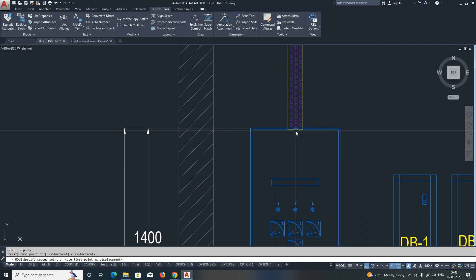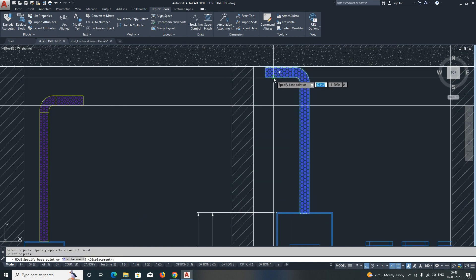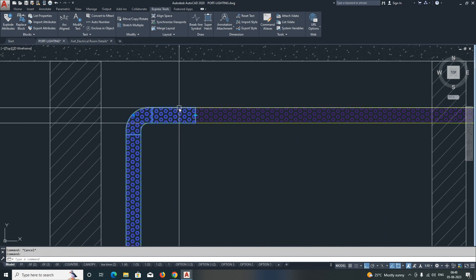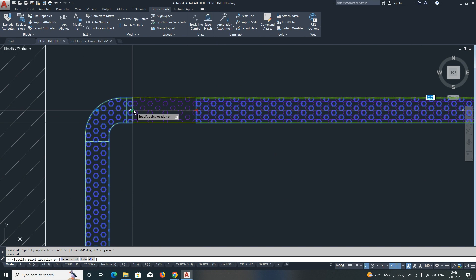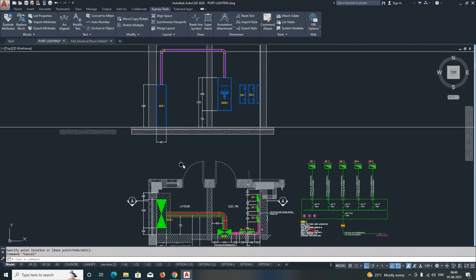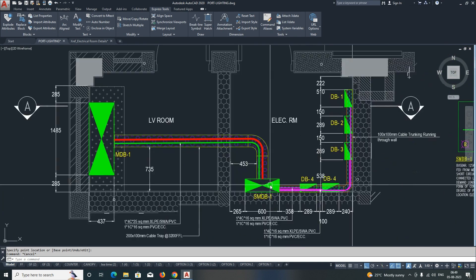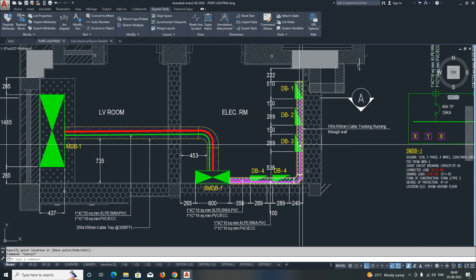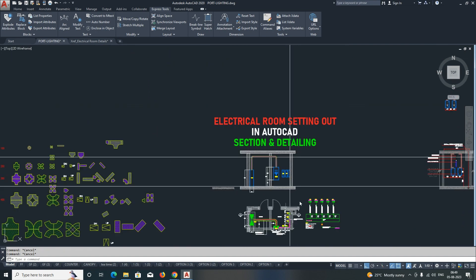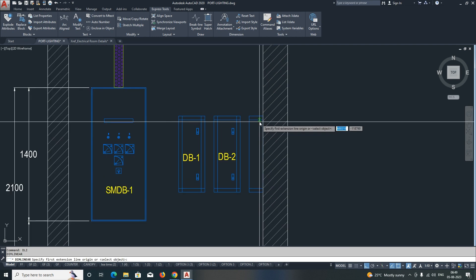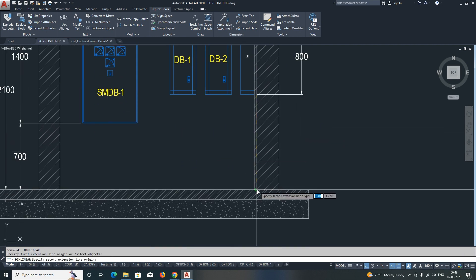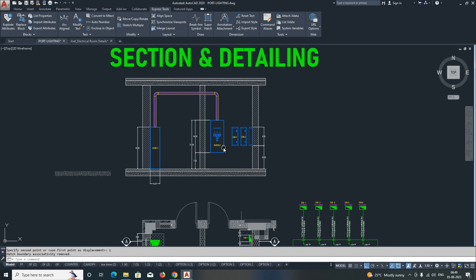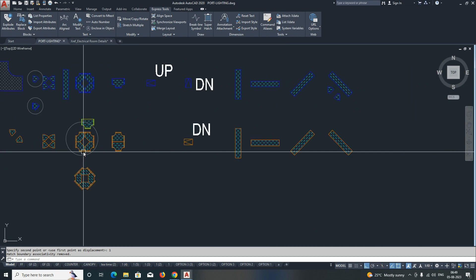Mirror this one — it will come to the SMDB panel. Give an offset and move it to that point so this cable tray connects to this panel. Stretch it to connect to the next panel as well. The meaning is: one cable tray is coming from the MDB to the SMDB. From the SMDB, one cable tray drops down to the DB panel, then trunking goes through the wall to connect further.